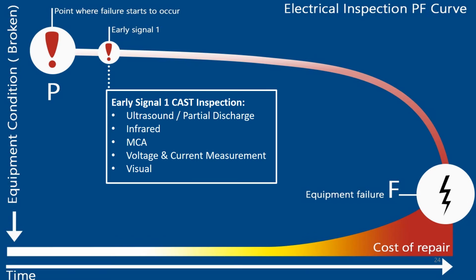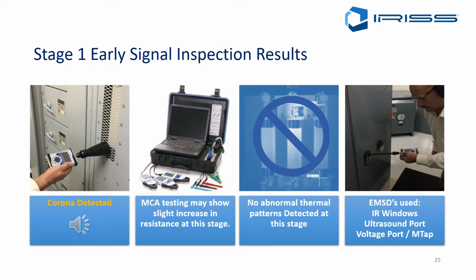Now, breaking into the PF curve, let's have a look at early signal 1. At this stage, we're going to use the primary tools in electrical inspections: ultrasound, partial discharge testing, infrared, motor current analysis or voltage and current measurement, and visual inspection. Looking at the results, what we would see at this stage is possibly we may detect corona, which sounds like this. And remember, corona is voltage dependent.